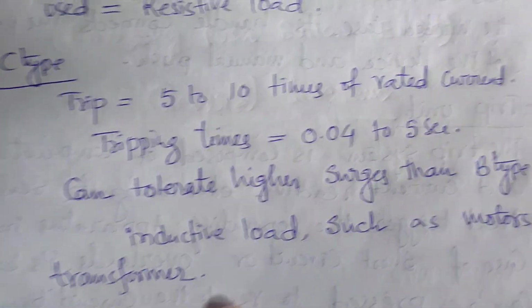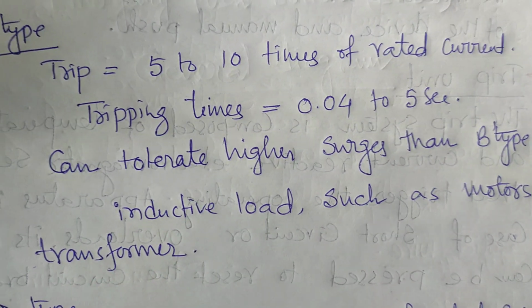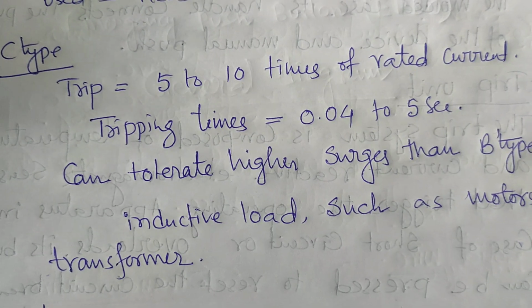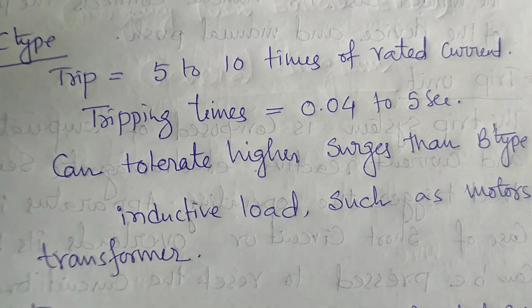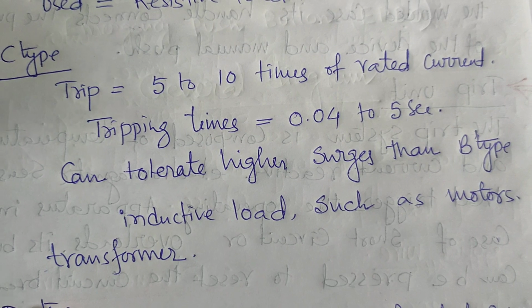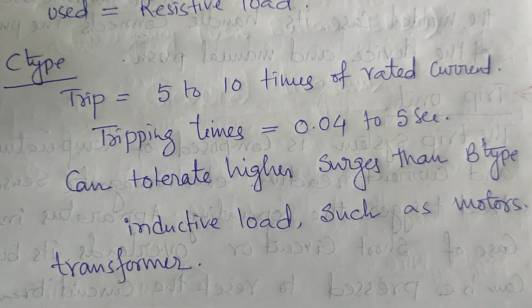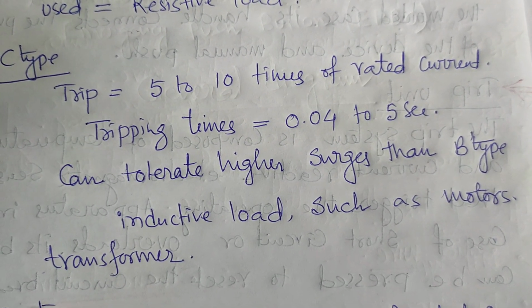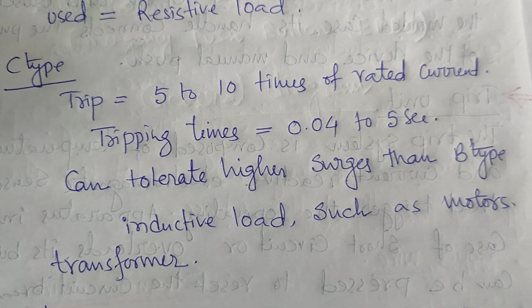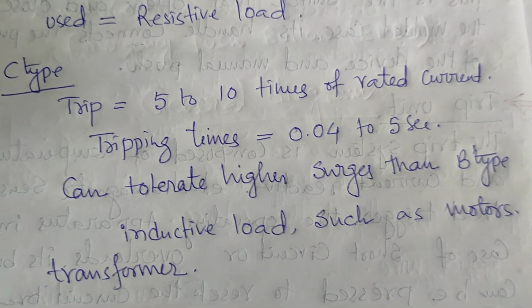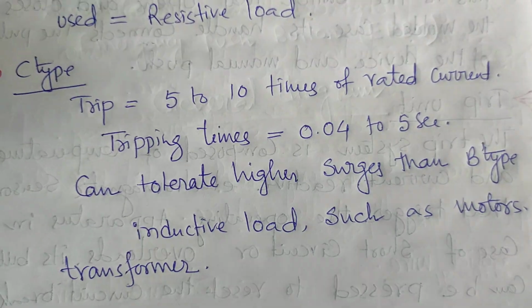It is used for inductive loads such as motor and transformer circuits. We use this type because surges come to the motors and transformers because of failures of the output lines. If a conductor snaps, a lot of voltage surge or current surge may occur. So for inductive loads we use the C type MCCB.